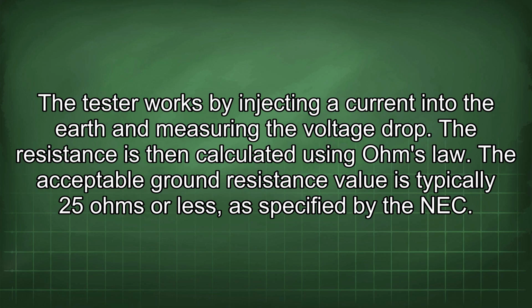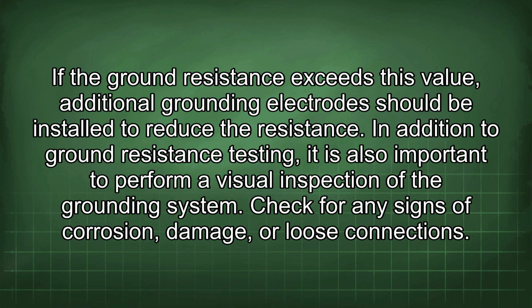The tester works by injecting a current into the earth and measuring the voltage drop. The resistance is then calculated using Ohm's law. The acceptable ground resistance value is typically 25 ohms or less, as specified by the NEC. If the ground resistance exceeds this value, additional grounding electrodes should be installed to reduce the resistance.